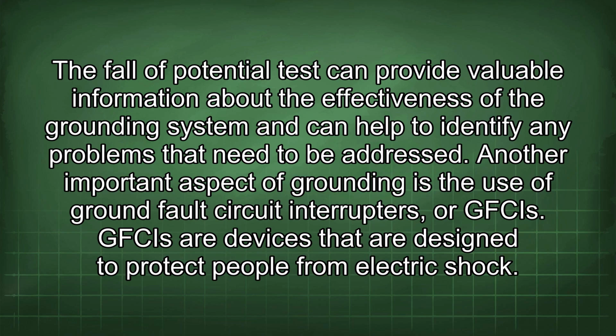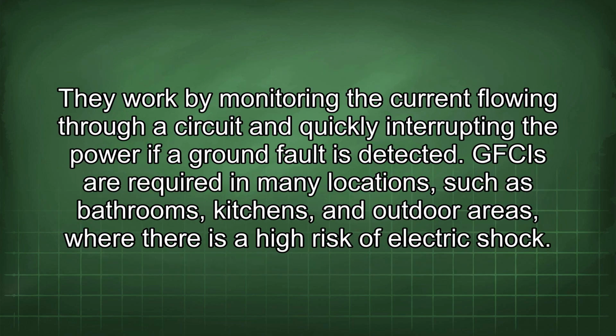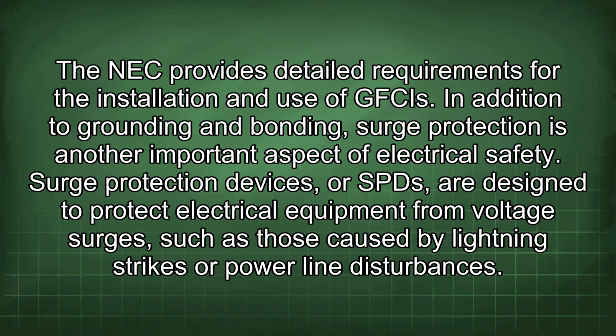Another important aspect of grounding is the use of ground fault circuit interrupters, or GFCIs. GFCIs are devices that are designed to protect people from electric shock. They work by monitoring the current flowing through a circuit and quickly interrupting the power if a ground fault is detected. GFCIs are required in many locations, such as bathrooms, kitchens, and outdoor areas, where there is a high risk of electric shock. The NEC provides detailed requirements for the installation and use of GFCIs.